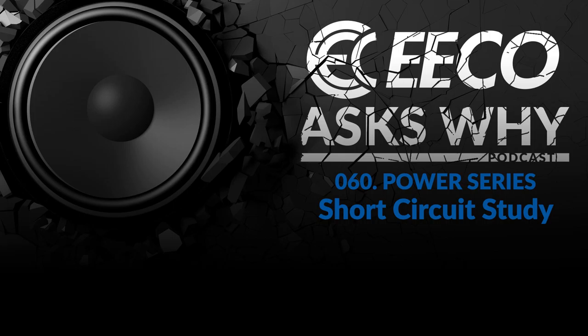We would go in and say, you know, breaker 53J is overduty by X percent. It would be highlighted in red, and we would flag it in the executive summary such that the end user would have the information there in a page or so: go look at this breaker, this board, whatever, this has been flagged as overduty. So it would be very easy to go and make those changes.